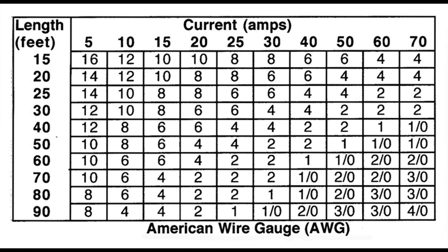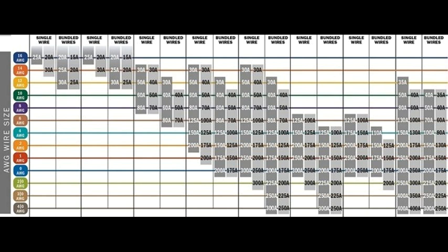Step 6, calculate wire and fuse sizes. Using information from calculating your loads, your schematic, and the location of your loads, you can determine the size of wire to use for each circuit, including the fuse size or circuit breaker.